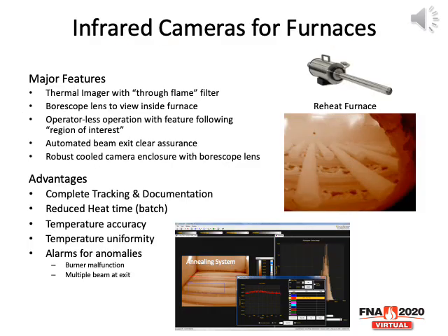Infrared cameras that are designed specifically for integration into furnaces are available that are very proven now to provide excellent data for the entire furnace or for many parts inside the furnace. These infrared cameras have a few features that make them reliable and for continuous 24/7 operation inside very high temperature furnaces. Key features include filtering that makes sure that the camera is measuring the parts or the refractory in the furnace and not measuring the flame for a gas fire type furnace. So this filtering makes sure that you don't have influence from the radiation that comes from the combustion process, but instead are measuring the infrared radiation from the parts under treatment.